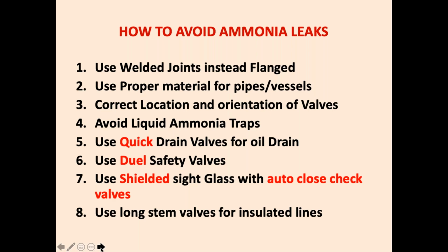Correct location and orientation of valves is important. All liquid line valves, just remember, I'm telling a very important point, should be with horizontal stem. That is, the stem should be facing towards your chest and not vertical top. Because if you have a vertical valve in a liquid line, there will be liquid trapped before the valve even when the valve is open. All these things we have given in our manual.